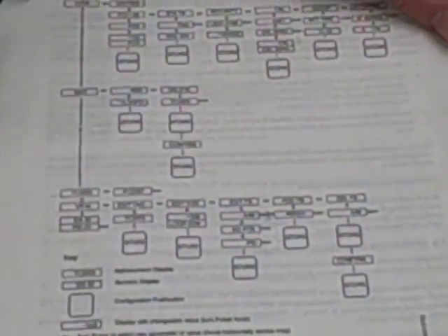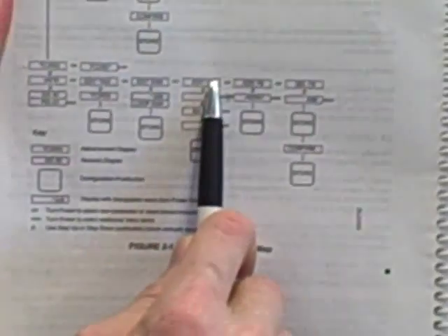To navigate, we go through this menu structure here, hitting the enter exit configuration button. We're going to navigate down, down and over to where it says edit function block, drop down, dial up the analog input number one function block and then modify those parameters.